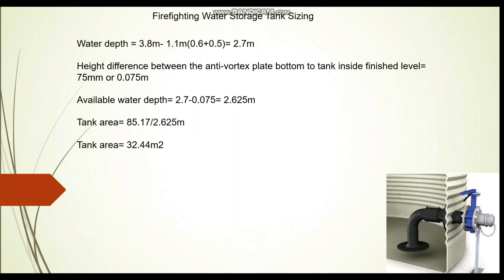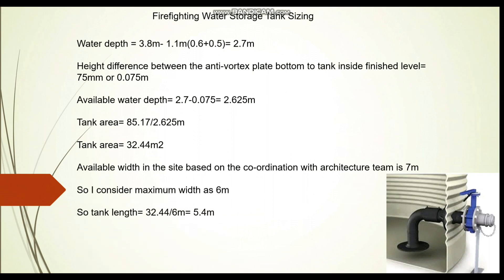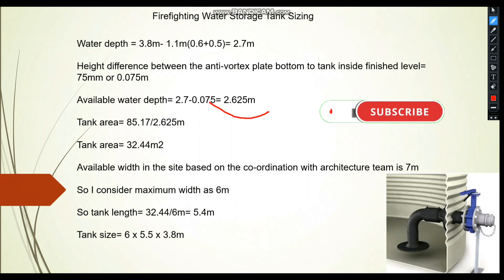To find the length and width, the available width on site — after coordination with the architectural team and allowing clearance for an adjacent electrical room — is limited to 7 m; we use 6 m as the tank width. Dividing 32.45 m² by 6 m gives a tank length of approximately 5.4 m, which we round up to 5.5 m. The final tank dimensions are 6 m × 5.5 m × 3.8 m (total height), with an effective water depth of approximately 2.625 m within that height.